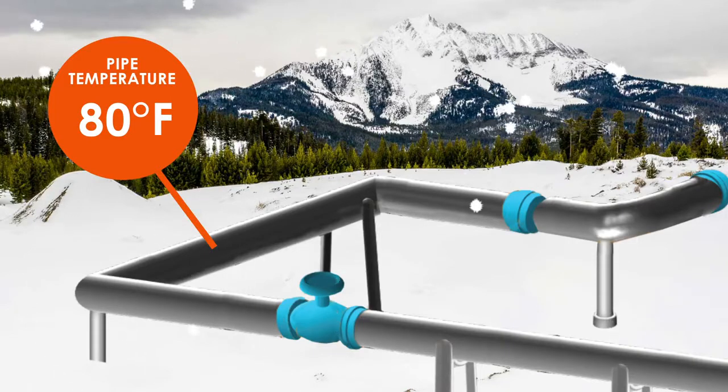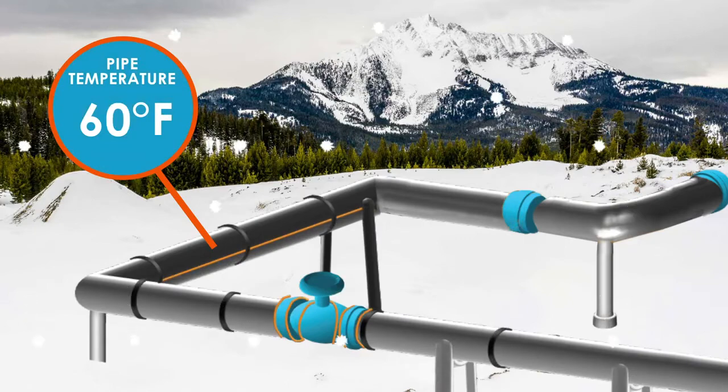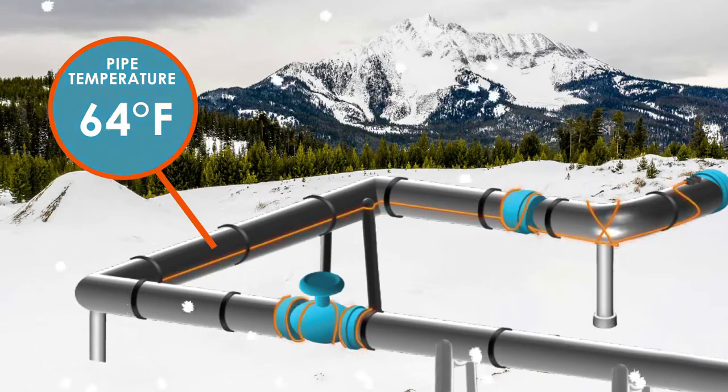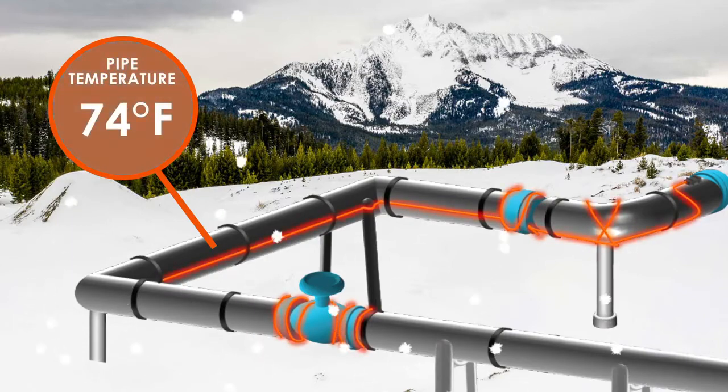Application of product is very different between heat trace and heat tape. If you have an R&D laboratory and are trying to heat a small exhaust line to 800 Fahrenheit, wrap it with that fiberglass tape, and you could have enough BTUs to achieve your desired temperature. Heat trace, on the other hand, is designed to maintain temperature in a pipe, not heat it up. If you're running a biodiesel plant in northern Montana, for example, and are trying to keep your lines at 80 degrees Fahrenheit when it's 20 below outside, the temperature will naturally try and equalize, so heat will flow from the pipe and into the ambient. This flow is partially stopped by insulation. Heat trace can make up the balance, allowing for pipes to maintain their desired temperature.